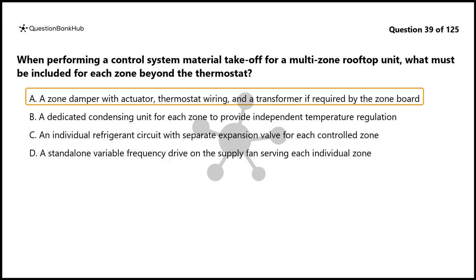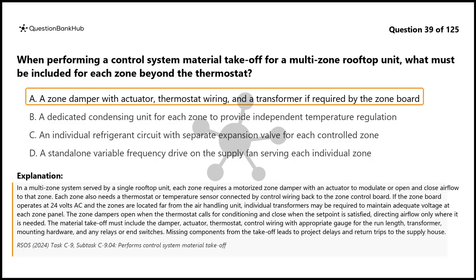The correct answer is A. In a multi-zone system served by a single rooftop unit, each zone requires a motorized zone damper with an actuator to modulate or open and close airflow to that zone. Each zone also needs a thermostat or temperature sensor connected by control wiring back to the zone control board. If the zone board operates at 24 volts AC and the zones are located far from the air handling unit, individual transformers may be required to maintain adequate voltage at each zone panel.